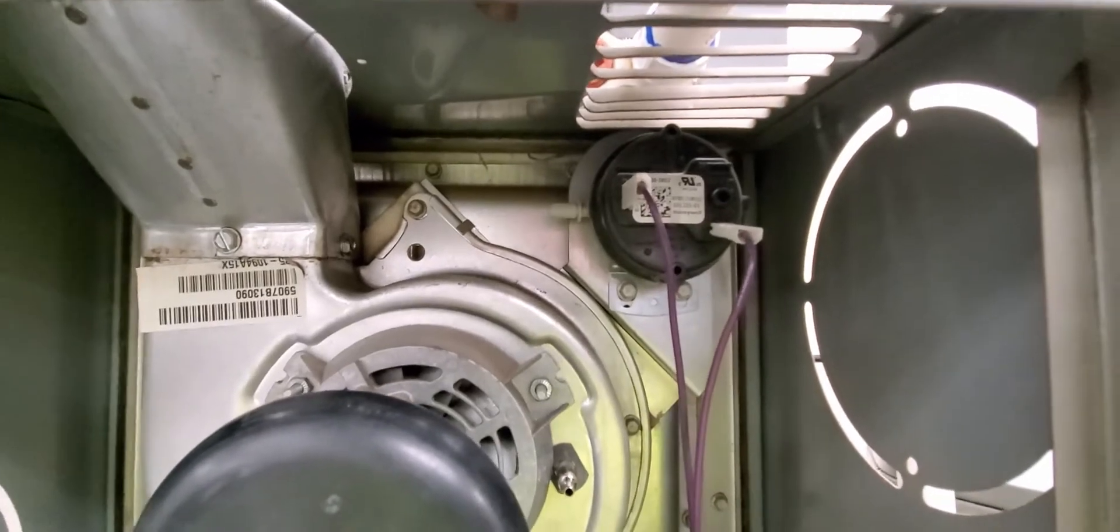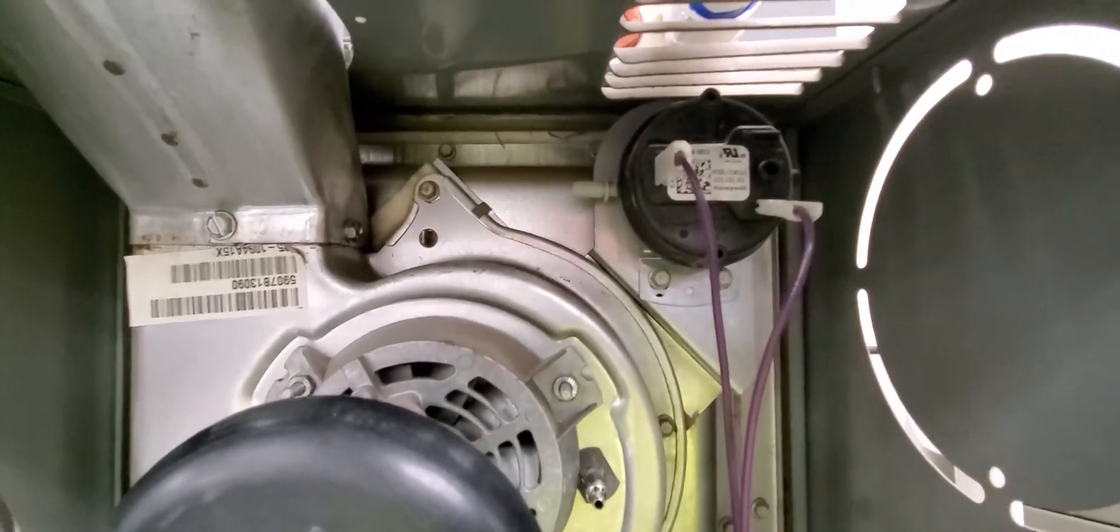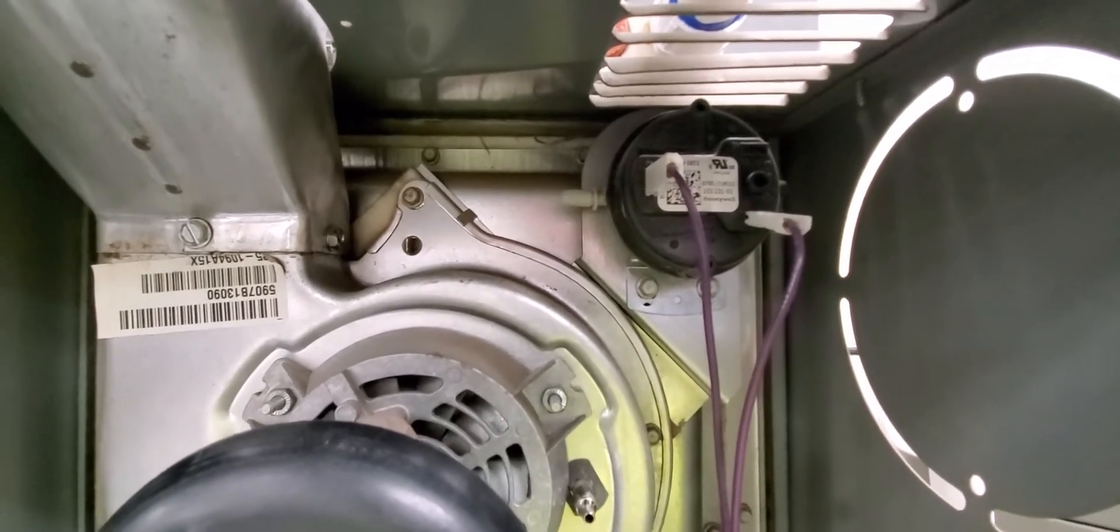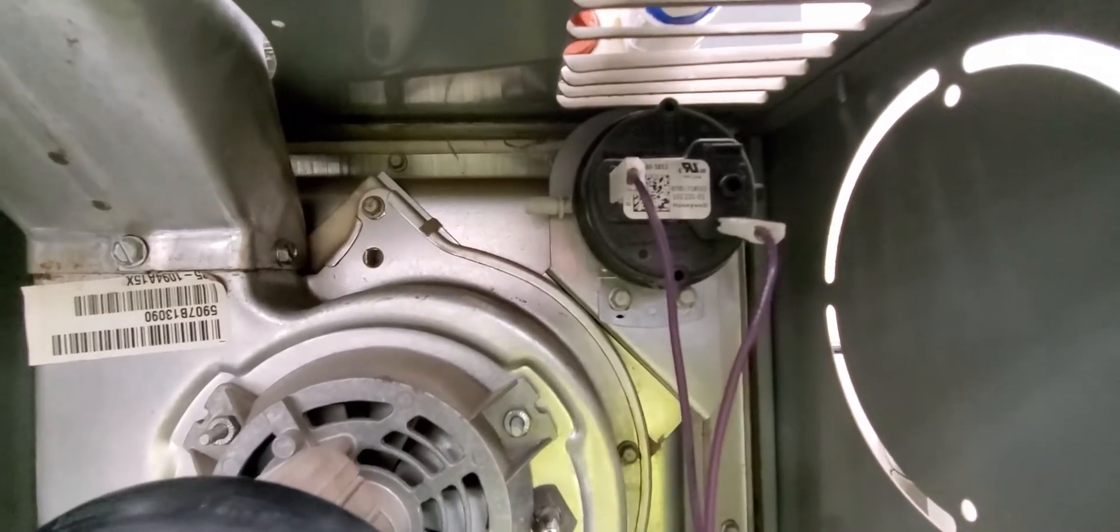Now on the pressure switch, never suck on the hose because you can actually damage the pressure switch by sucking or blowing on it. It's only working at 0.4 inches of water column.